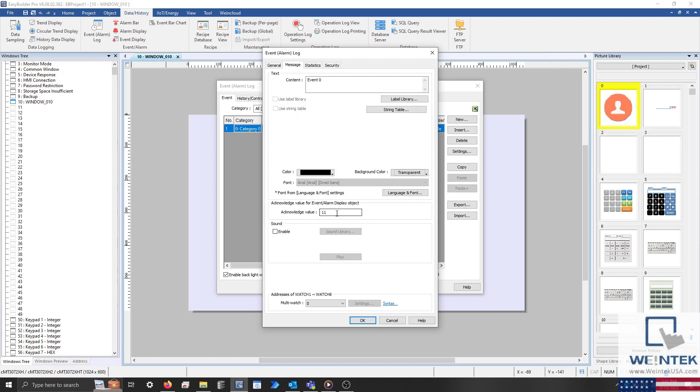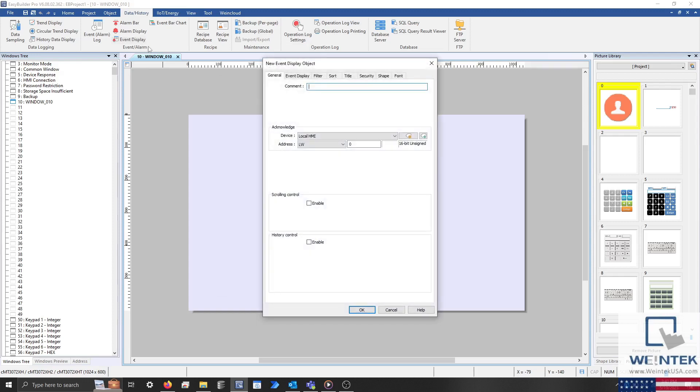Now what this does is when you click on an alarm within the event display, the acknowledge value configured for this alarm will be written to the acknowledge address. You can use this feature in a variety of ways, such as to acknowledge the alarm within the PLC or open a pop-up window on the HMI.